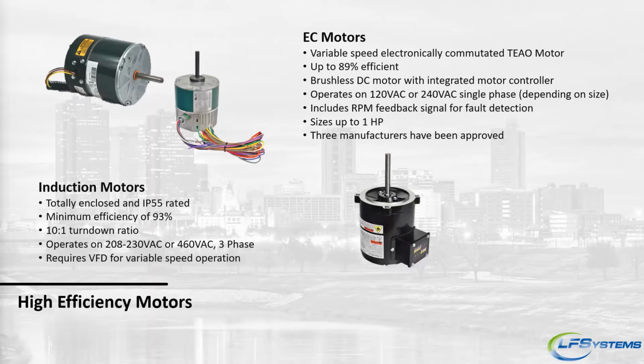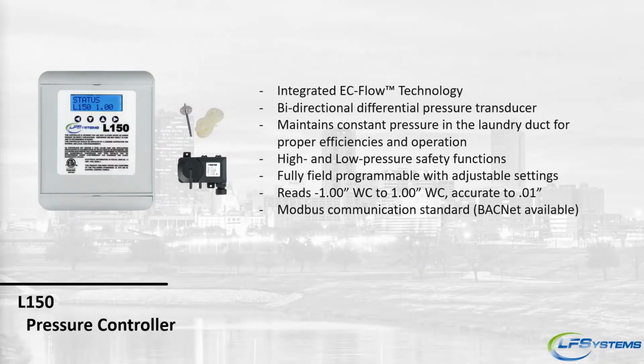Nice thing is when you buy this package from us, we do supply the VFD, so it's pre-programmed straight out of the factory to run with our control package. That controller is our L150 I mentioned earlier. It has the same EC flow technology as all our other controls. It is a true bi-directional controller with transducer, so we can read positive and negative across 0. It offers a high and low pressure safety function. It is field programmable, although most of the settings are going to be preset from the factory.